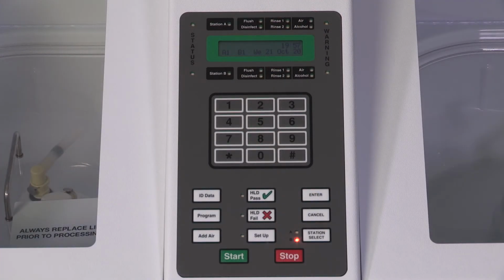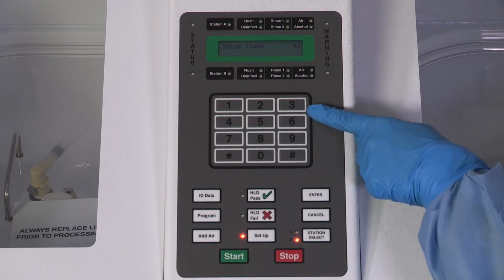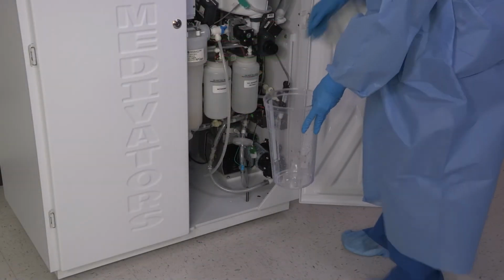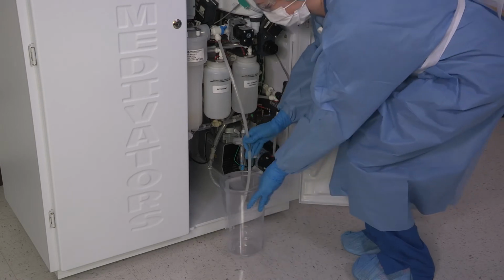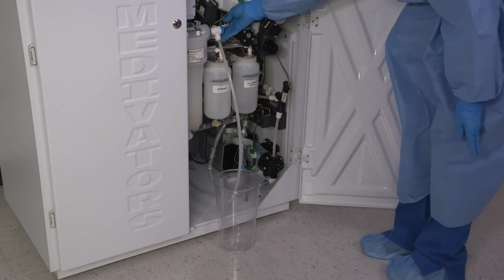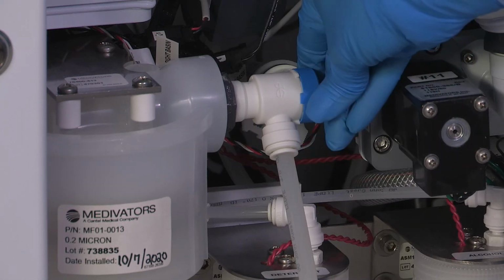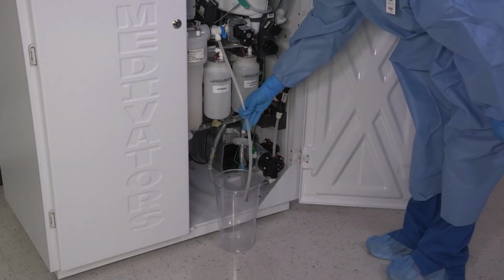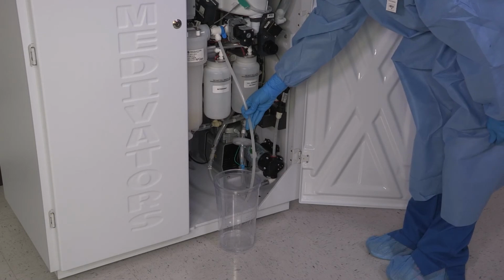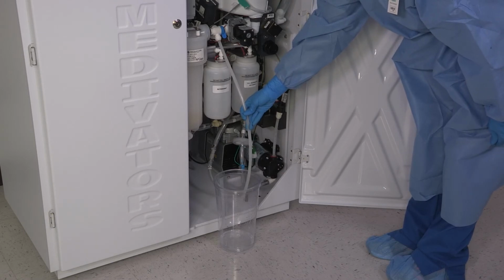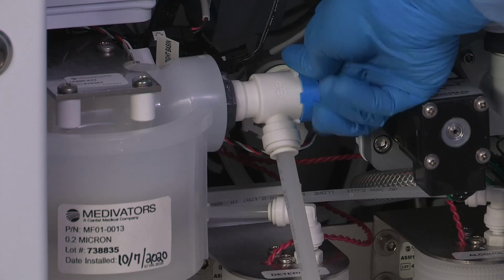To release the pressure in the water lines and on the filter housings, press Setup, 43, Enter. Direct the purge line into a container that can hold a minimum of 1 liter of fluid. Slowly open the handle on the air bleed valve to allow the water to drain into the container. Once the water flow reduces to a slow drip, close the air bleed valve.